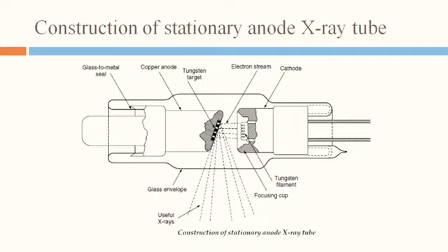These X-rays are produced in a specially constructed glass tube, which, as you can see in the diagram, comprises a source for the production of electrons, an energy source to accelerate the electrons, a free electron path, a means of focusing the electron beam, and finally a device to stop the electrons. Now we will study how this exactly works.